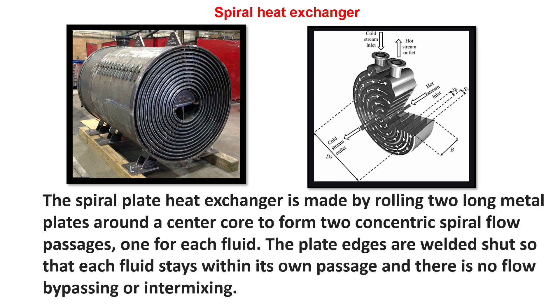The spiral plate heat exchanger is made by rolling two long metal plates around a central core tube to form two concentric spiral flow passages, one for each fluid. The plate edges are welded shut so that each fluid stays within its own passage and there is no flow bypassing or intermixing.